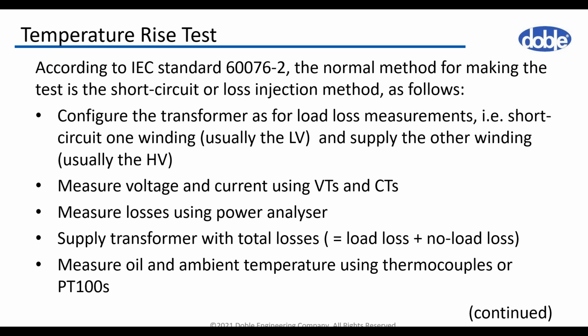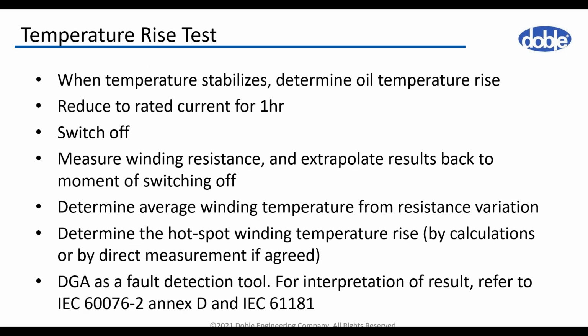Ambient temperature is measured by sensors placed on specific locations around the transformer. Top and bottom oil temperature is measured in dedicated pockets on the top of the cover and radiators inlet and outlet headers. At the beginning of the test, the sum of load loss and no load loss are applied. Once stable condition is established, we can determine oil temperature rise. Then we reduce the current to the rated one for 1 hour, followed by switching off.